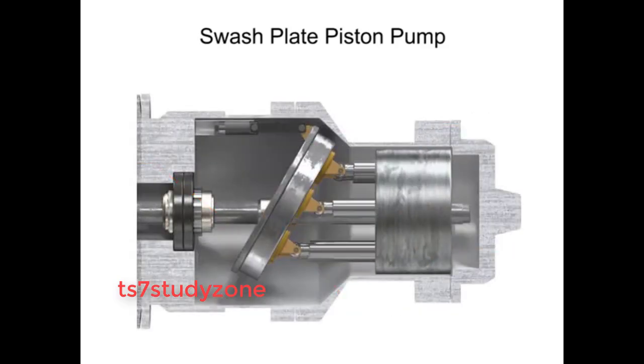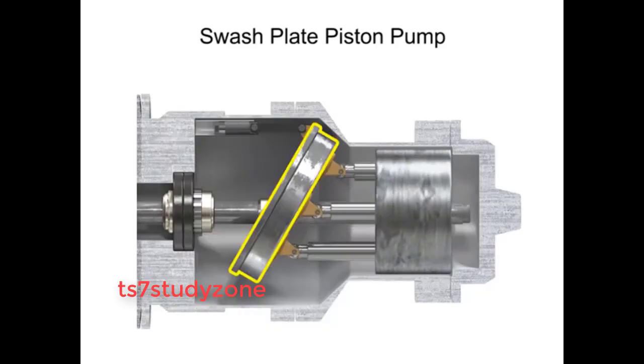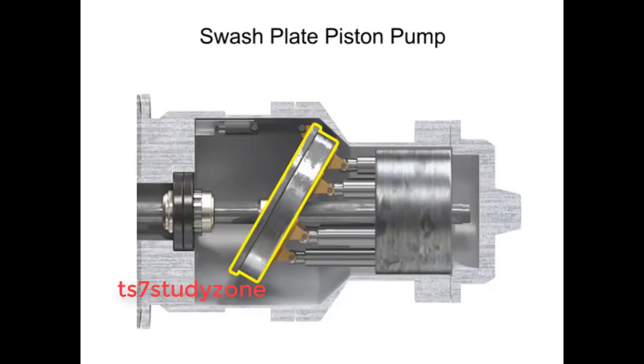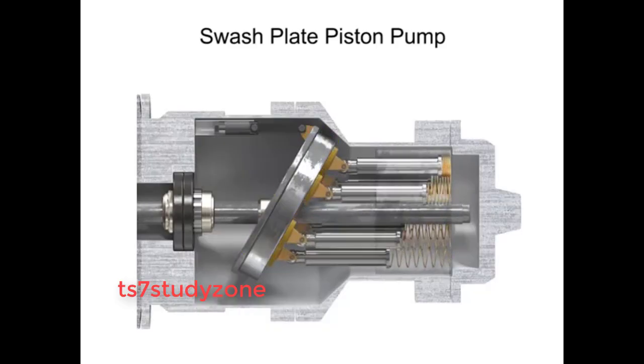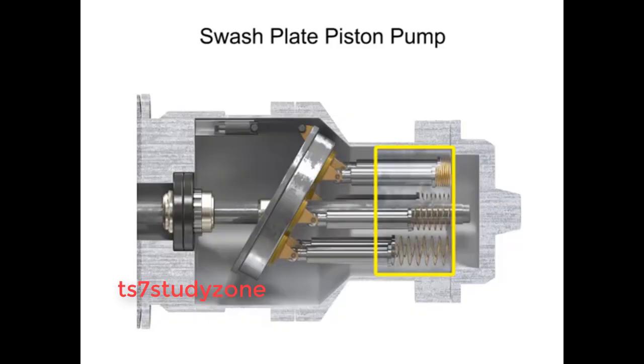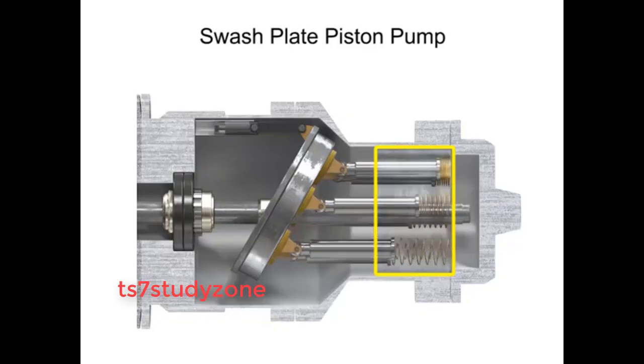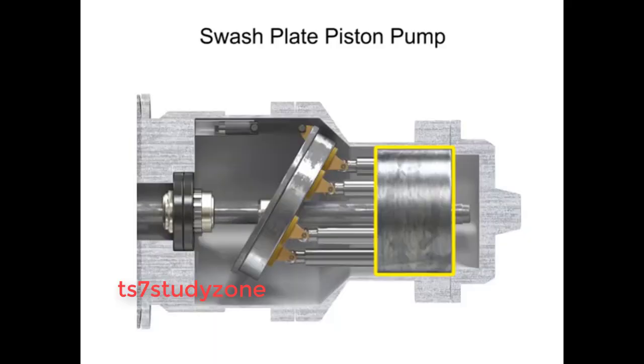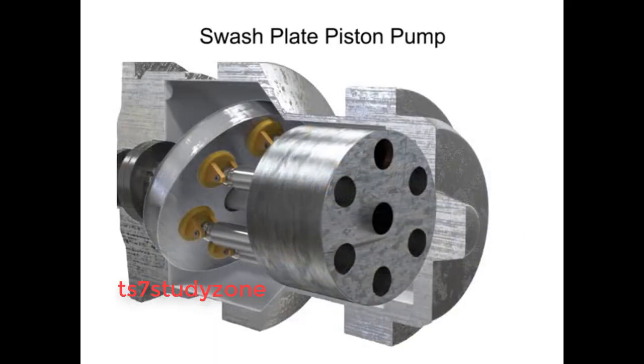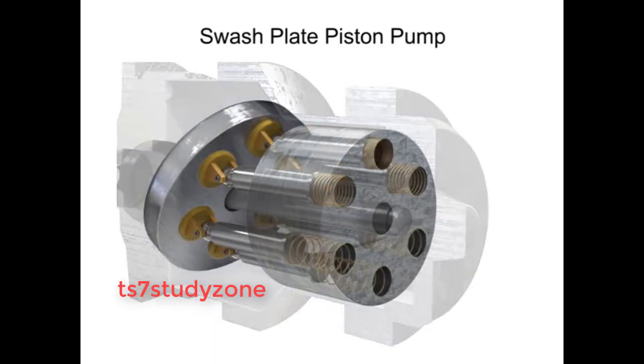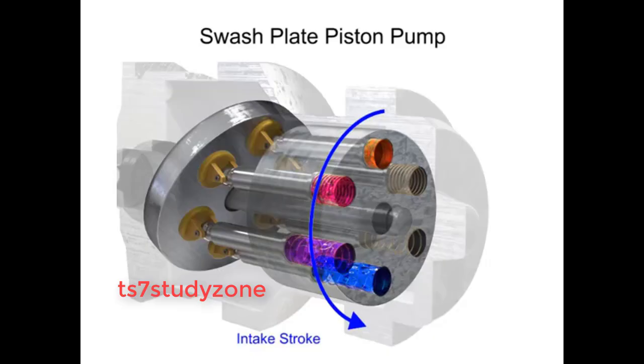As the shaft rotates, the pistons move against the swashplate, causing them to reciprocate within the piston block. The pistons create a vacuum that forces fluid in during half a revolution and expels fluid during the other half.